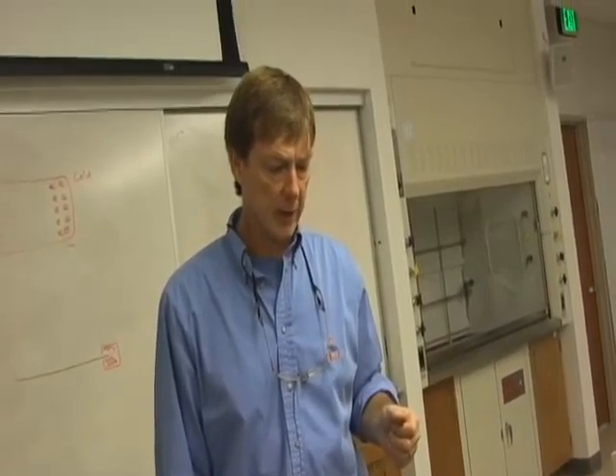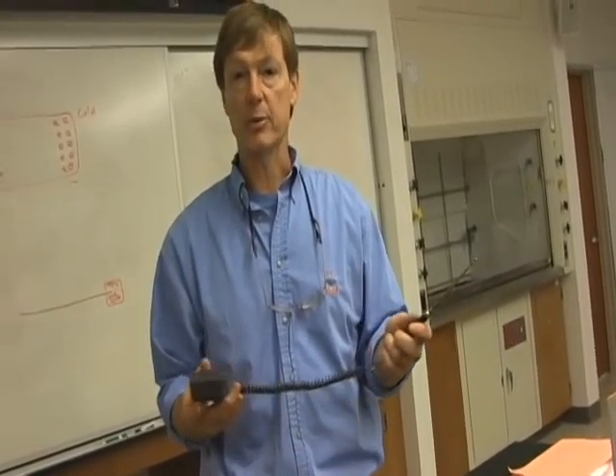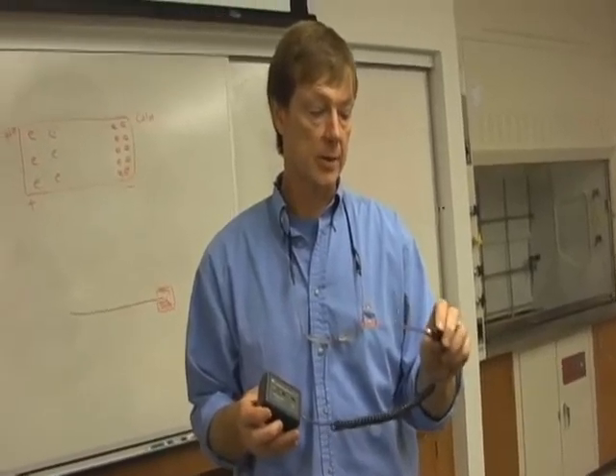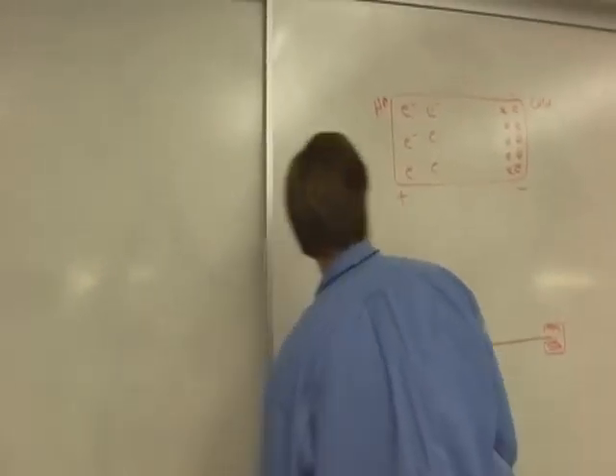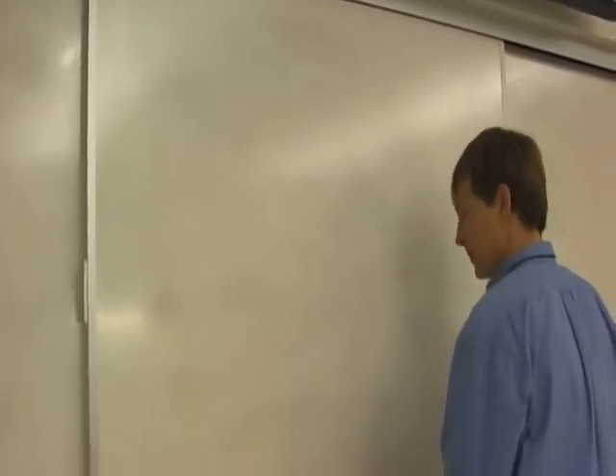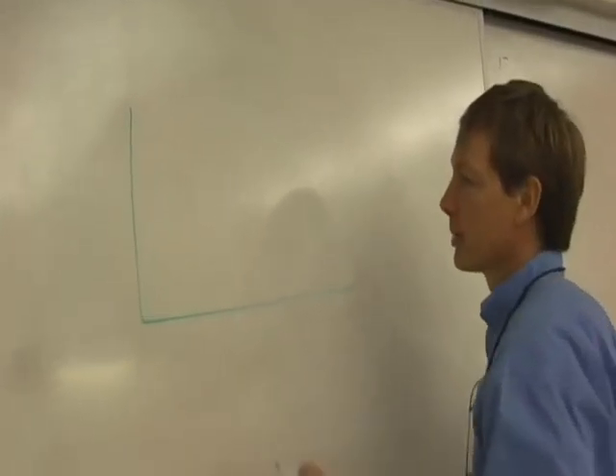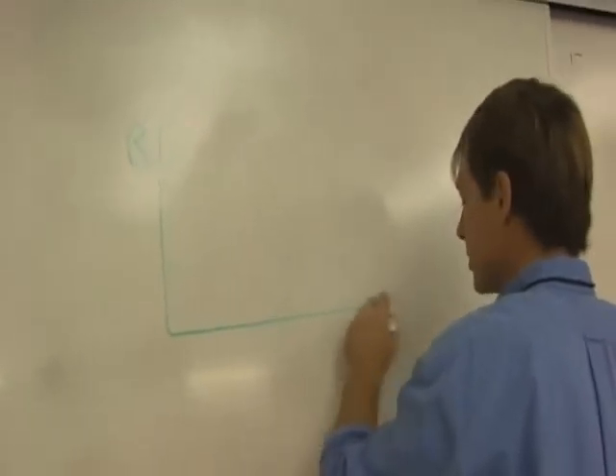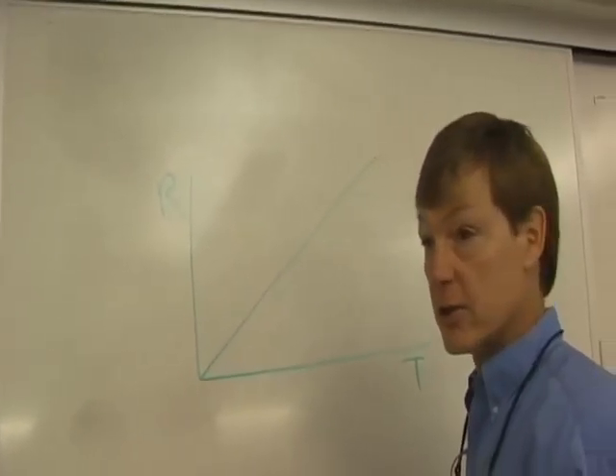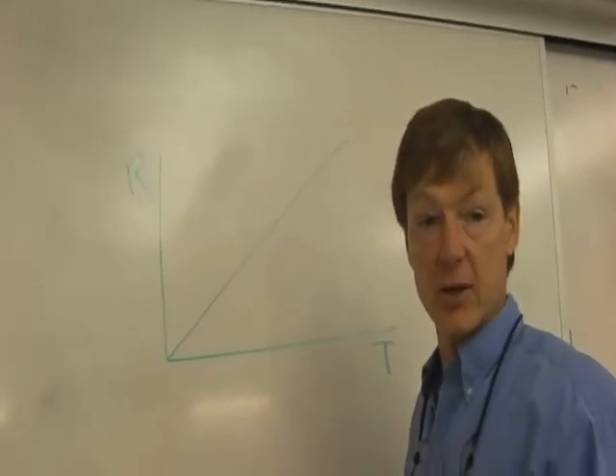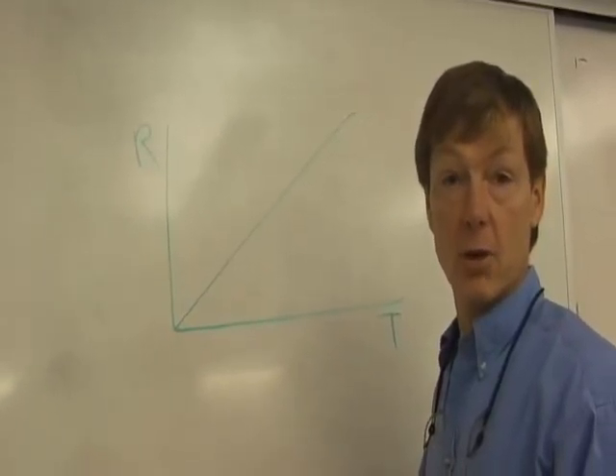Another way to measure temperature is with resistance. It's resistive temperature devices or platinum resistance detectors. This right here. Basically, what it says is the way it works is if I heat up a conductor, generally its resistance will go up. And there's a correlation between resistance and temperature for these resistive temperature devices. And it's pretty much a nice straight line. So as the temperature heats up, the resistance of the device goes up. If you're running a voltage across it, that means the current is going to drop. And that change in current, you can correlate that directly to the temperature.